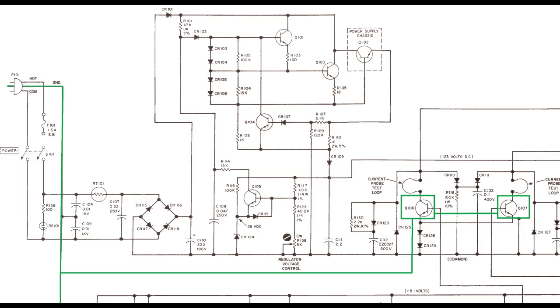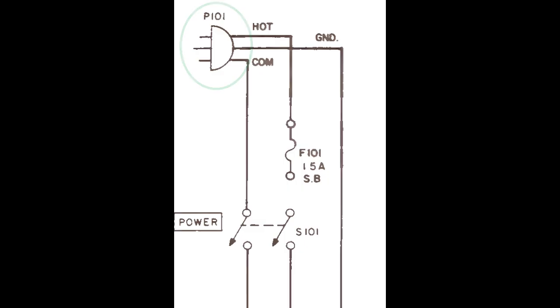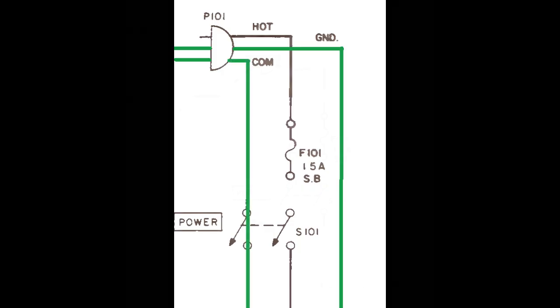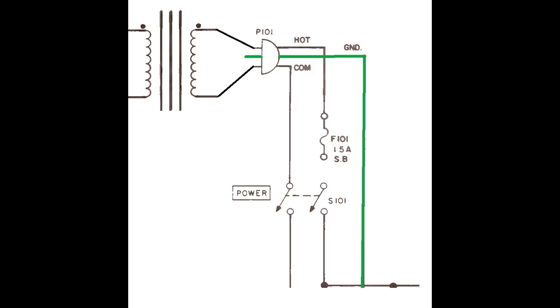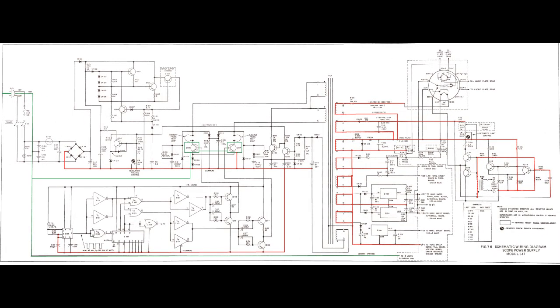Now one might think, ground is ground, no problem, right? Well, no. Looking back at this part of the schematic, you can see the good old P101, or the mains plug, and you can see the ground connection coming off here. But of course here I am in North America, and that ground line goes up and somewhere into the bowels of my house, where it is connected back to the common side of the plug, so I actually get this. Now, as long as I was using an isolation transformer, I was fine, as there was never a connection between ground and common. Take that isolation transformer away, suddenly you've connected ground to common, and zap! Everything in red should be 0 volts. And after that short, I have up to 120 volts on the ground rail.